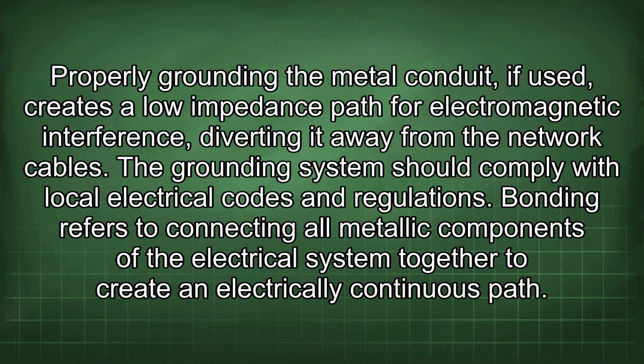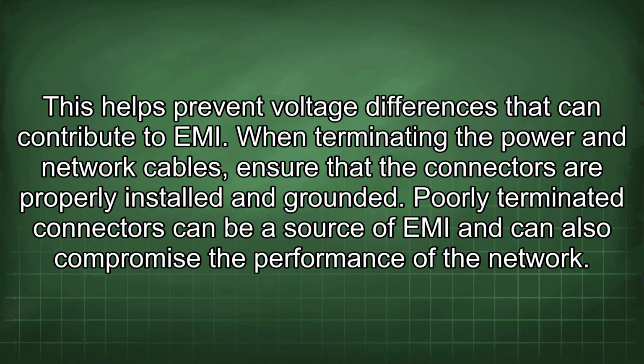Properly grounding the metal conduit, if used, creates a low impedance path for electromagnetic interference, diverting it away from the network cables. The grounding system should comply with local electrical codes and regulations. Bonding refers to connecting all metallic components of the electrical system together to create an electrically continuous path. This helps prevent voltage differences that can contribute to EMI.